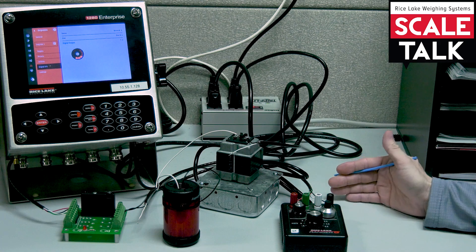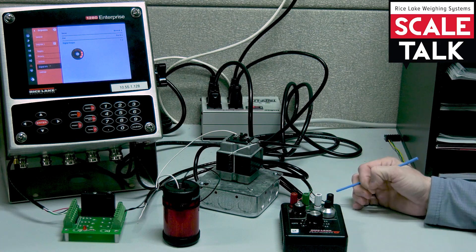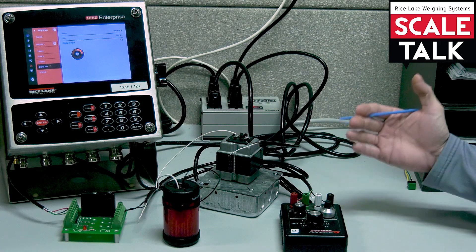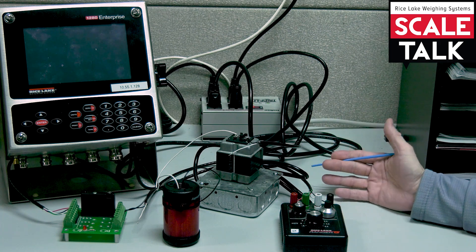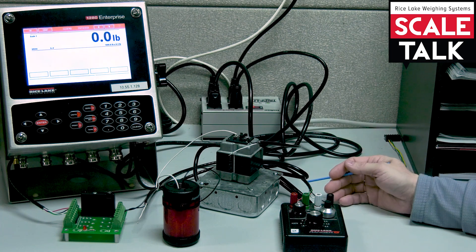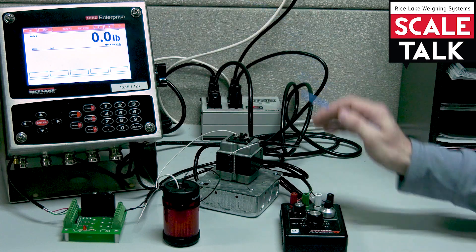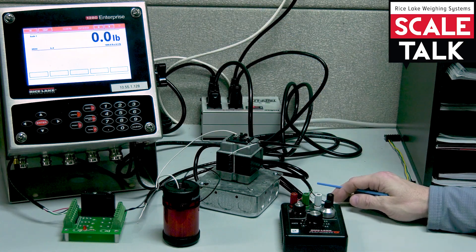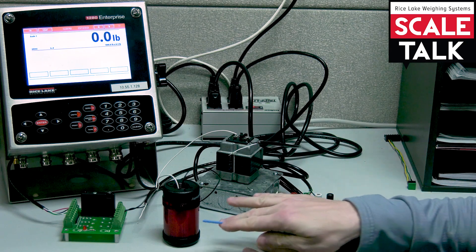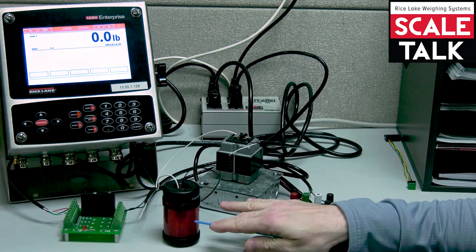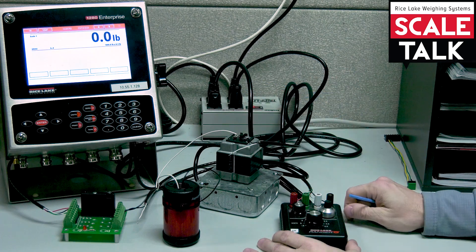Now remember, the free running set point is always being evaluated. This was a 500 pound set point set to trip higher. So in this case I have no weight on the display currently. When I ask it to trip higher at 500 pounds, my expectation is that my light is going to come on once I exceed 500 pounds.